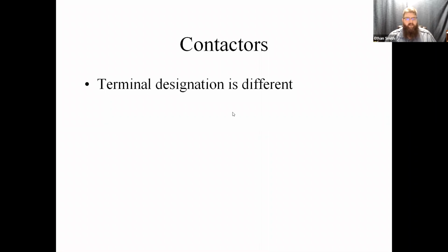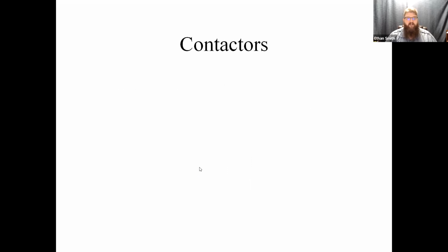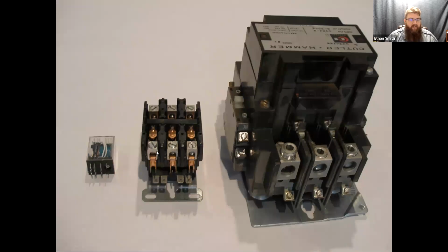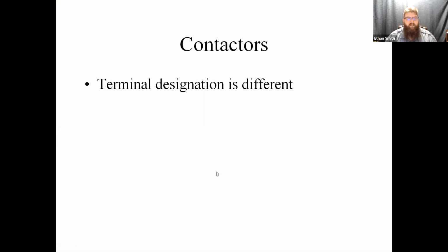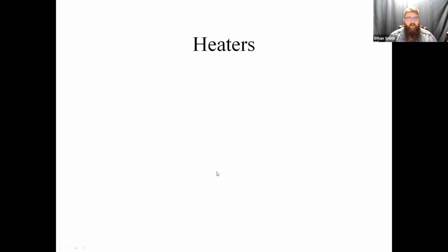Contactors sometimes have different terminal designations, especially if they're three-phase. You'll have L1, L2, and L3 on one side, and then you'll have T1, T2, and T3 on the other side. So we use this a lot. That's usually labeled on the contactor. It's a little tough to see in this picture back here, but if my photo was a little higher resolution, you'll notice that these are labeled L1, L2, L3, and T1, T2, T3 back here. Same thing. We've got a coil and a set of switches on them, guys. Any questions about diagnosing contactors, relays, switches, anything like that?